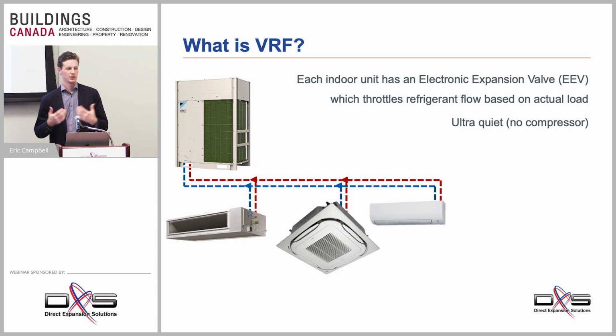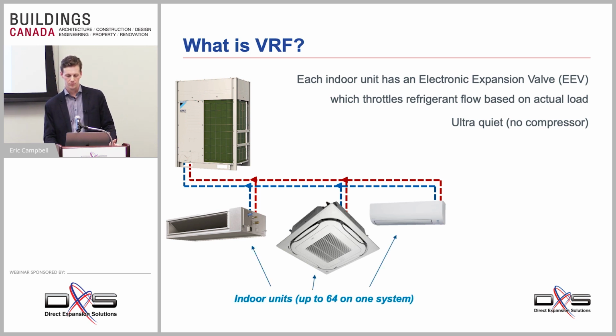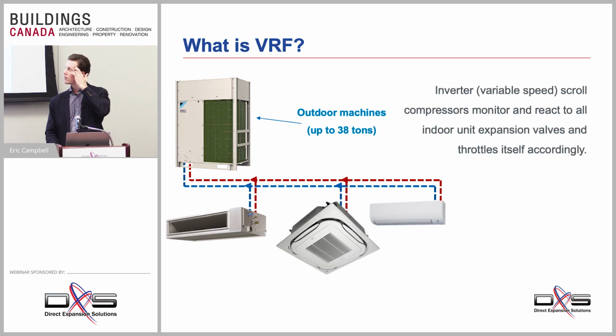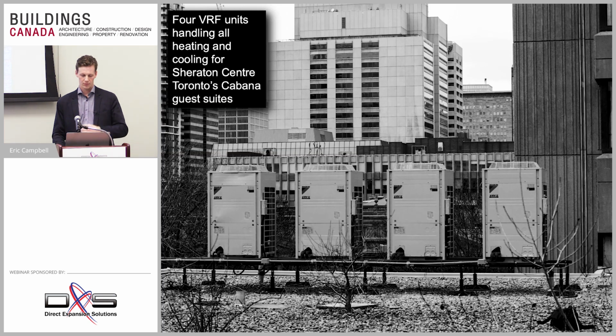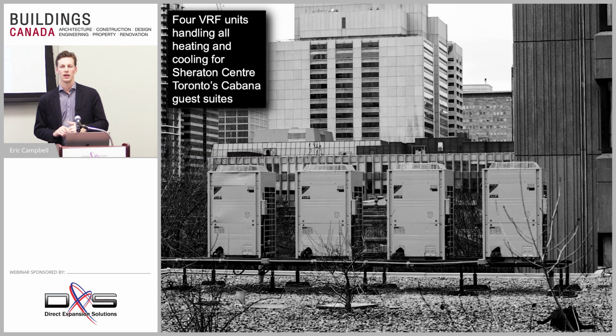Because those indoor units are basically just what we call fan coils, with a fan, that expansion valve and the coil, there's very little sound. That fan runs continuously, so it's not kicking on and off like a traditional single speed fan in your home, which also increases occupant comfort. And again, the compressors in the outdoor units are variable speed and optimized for part load efficiency. They modulate based off of the communication signal they're receiving from all those indoor units, telling them what speed to run at. These are very commonly used in the commercial area, we're starting to get them into condos, and we're also looking at a lot of retrofit opportunities to use these air-cooled machines.